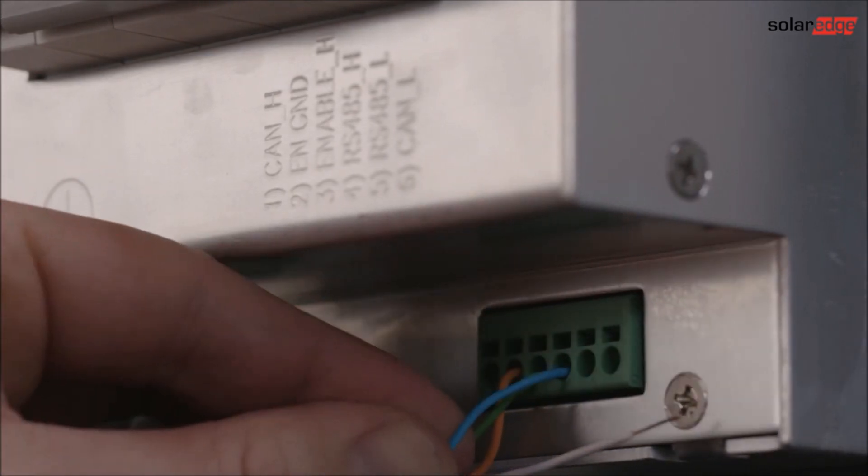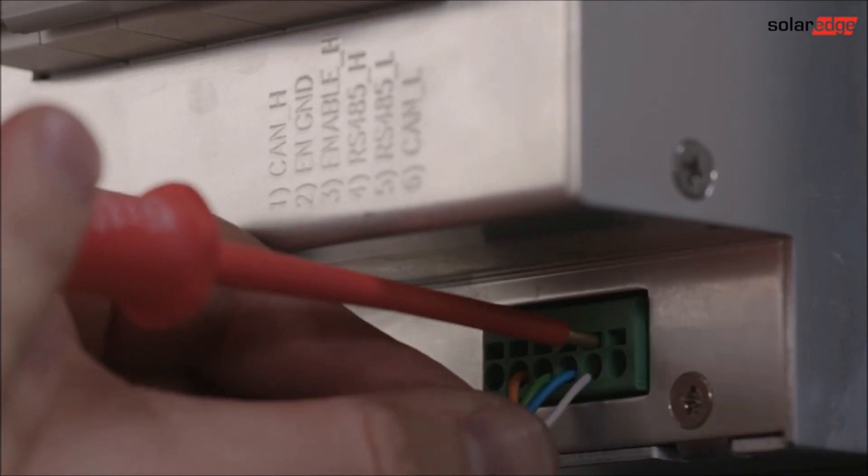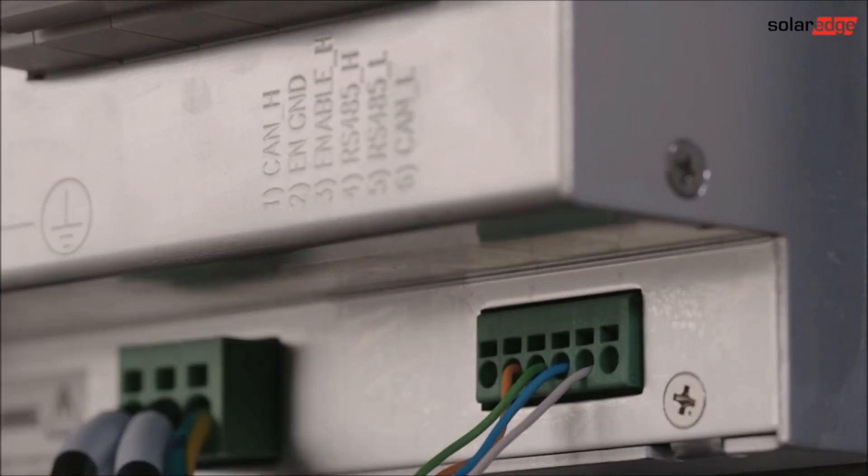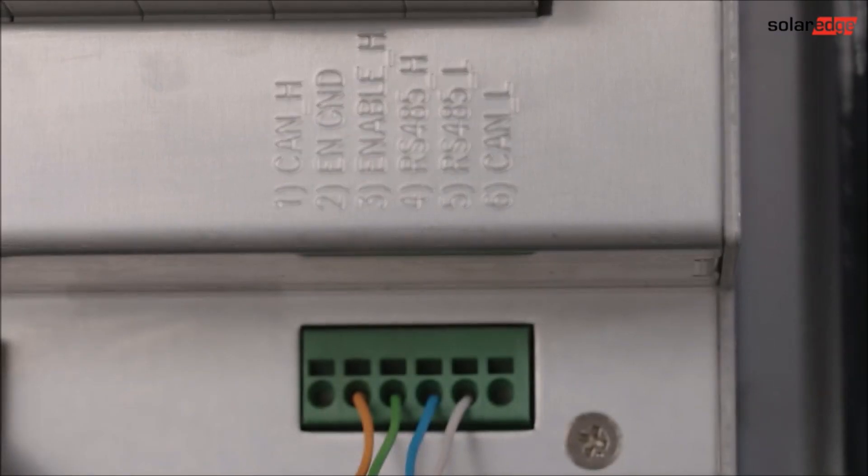It is mandatory to put the RS485 high and low connections on one twisted pair. The latest wiring information can be found in the storage wiring guide.